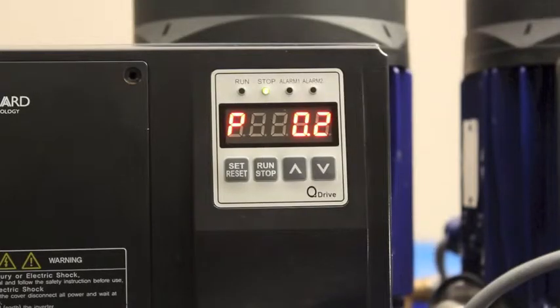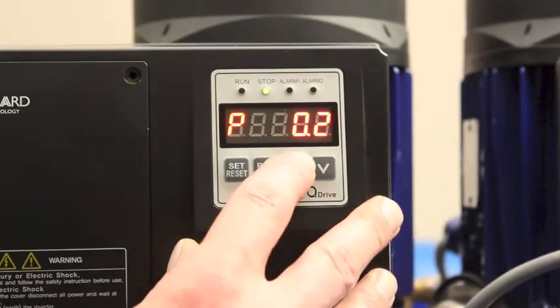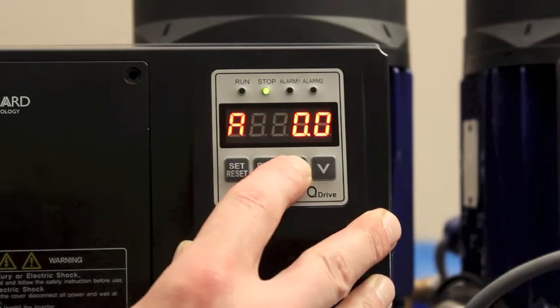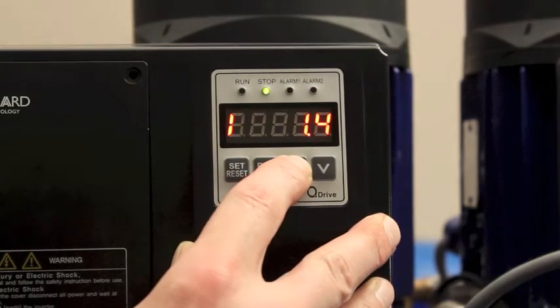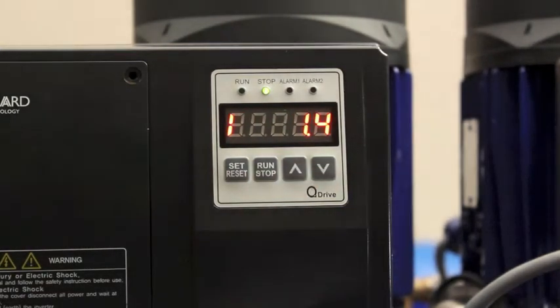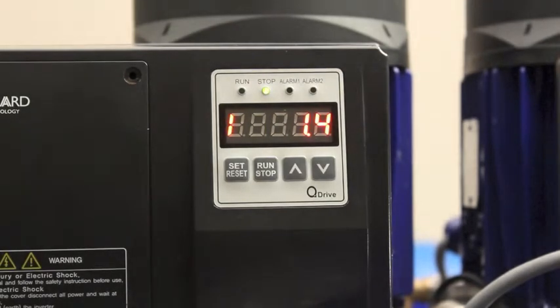While the pump has been stopped, we need to check what the static pressure within the system actually is. When we know this, then we can use the up and down buttons on the Q Drive to find I and O, which represent the inlet and the outlet. Do not confuse a large O and small o, which is a percentage output and should be ignored in this case. Both I and large O should display the same pressure and should also be the same as the system static pressure, which in this case is 1.4 bar.